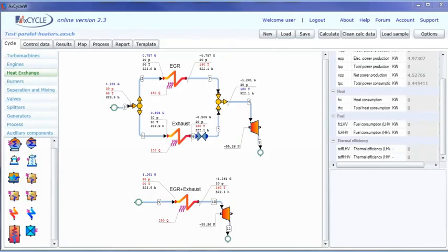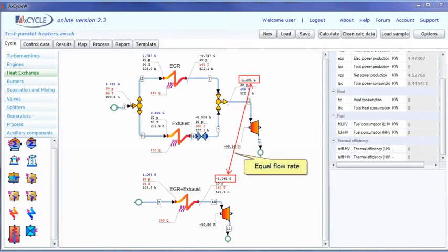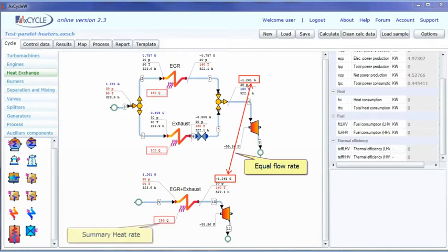As we are focused on overall waste heat recovery system performance, it is convenient to substitute two heat exchangers with a single equivalent heat source. In this case, fixed boundary conditions are used for temperature downstream of the heat sources. Mass flow rate through each is calculated; total mass flow rate is 1.261 kilograms per second. Two parallel heat sources are substituted with a single one with total heat rate, and mass flow rate is equal to the case with two parallel sources.